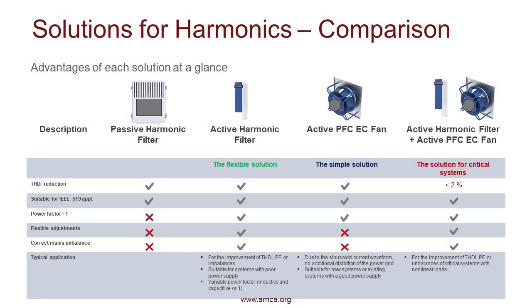It's increasing your power factor. It's a flexible solution, obviously, and it's correcting your mains unbalance. And then you have the simple solution, so your active PFC EC fan. So no additional wiring, no additional space within your cabinet. It's reducing your total harmonic distortion and it's increasing your power factors.